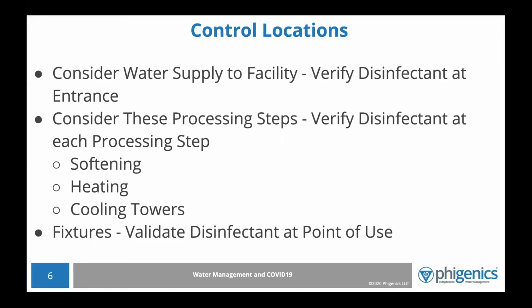Without disinfectant coming in there in a no use or a low use situation, you're going to start to have trouble. Once the water enters the building, you have some processing steps that you need to take a look at. And I will start with a typical hospitality or healthcare facility. One of the very first processing steps that people do and don't consider a processing step is softening. When water use drops, the softeners may become fouled and can actually remove any disinfectant that came into the facility. We need to look after softening, especially on water that's softened for potable uses such as heating. Make sure that you have disinfectant directly after the softeners.